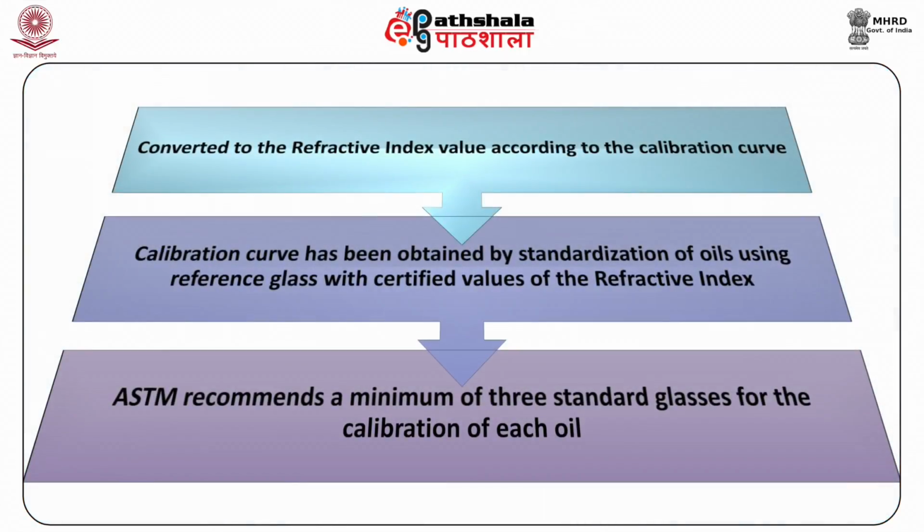These values are then recorded as the match temperature on cooling and the match temperature on heating, which are then averaged to give the match point temperature of the sample. This is, as discussed earlier, converted to the refractive index value according to the calibration curve.